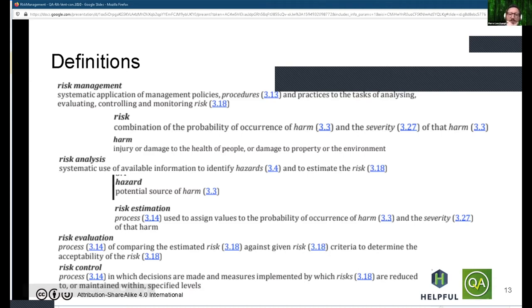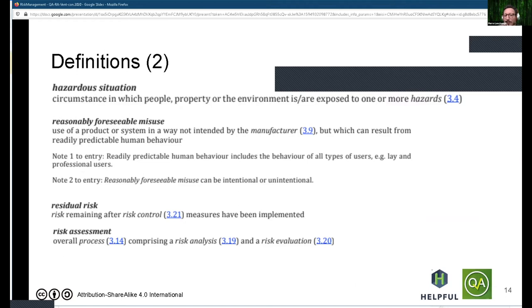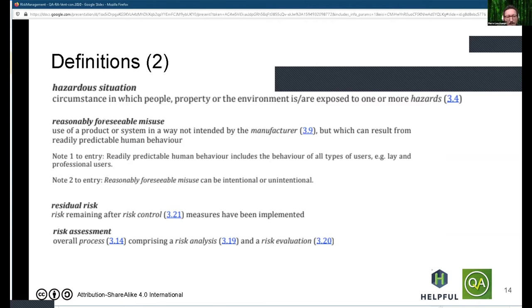A hazardous situation is defined as a situation in which property, environment, or people — of course that's the main focus for medical devices — would get exposed to one or more hazards. The risk management process, as mandated by ISO 14971, also requires manufacturers to design for reasonably foreseeable misuse. That's a very important concept and a relatively recent addition to these standards.